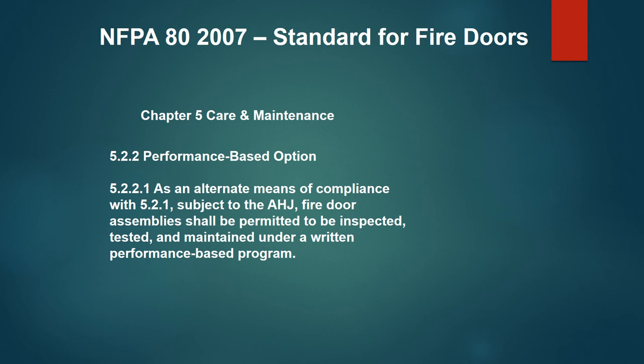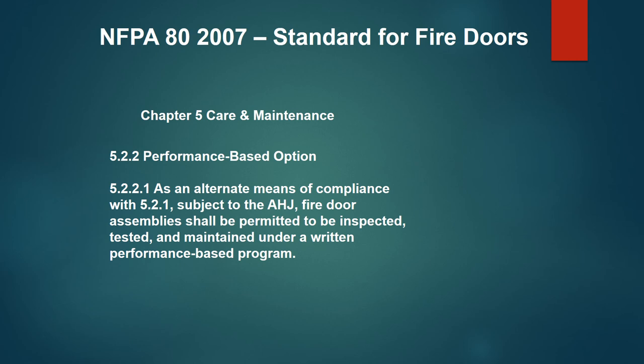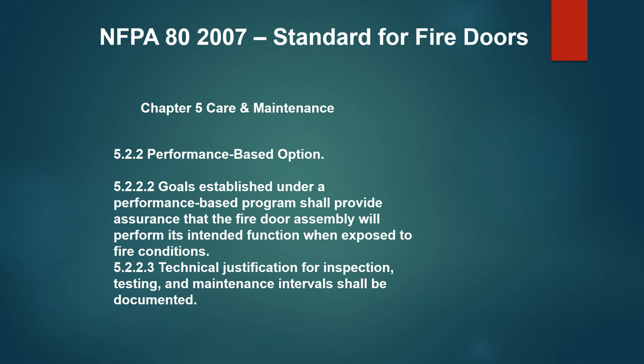The key is good data, good information, and a good inventory. Rotate which doors you check — don't always check the same hundred. Do a risk assessment: doors in high-use or high-equipment areas, or those more prone to failing, should be inspected every year regardless. Apply performance-based sampling to the lower-risk balance. The goals of the performance-based program shall provide assurance the fire door assembly will perform its intended function when exposed to fire, and the technical justification for inspection and maintenance intervals must be documented.